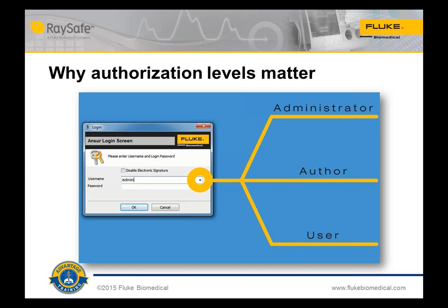Passwords need to be controlled, with a process provided for when passwords are lost, forgotten, or when an associate leaves the company. Electronic signatures and their control have special requirements documented in 21 CFR Part 11. The requirement for control is managed by also having those authorization levels.